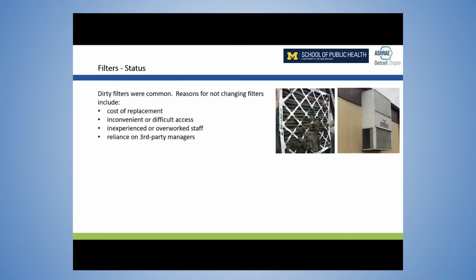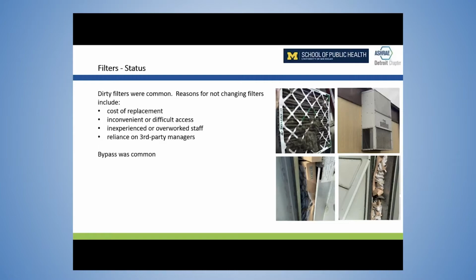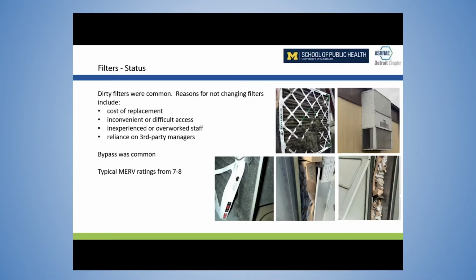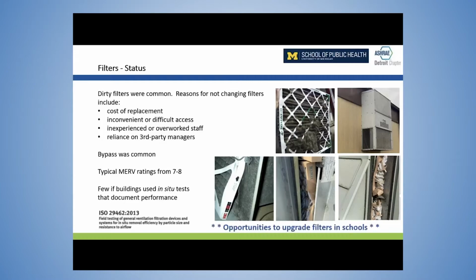So what do we find in schools in the Midwest? We find a lot of dirty, overloaded filters. A number of good reasons for not changing them out are listed here. We find lots of filters misinstalled, gaskets missing, and bypass quite common. We find both dirty filters plus bypass. And we typically find MERV ratings from 7 to 8 as the default. And then hardly any of the schools had in-situ tests that document performance of their air filtration, much less the HVAC system, despite the existence of a standard for doing so. So I think there are many opportunities to upgrade filters in schools.